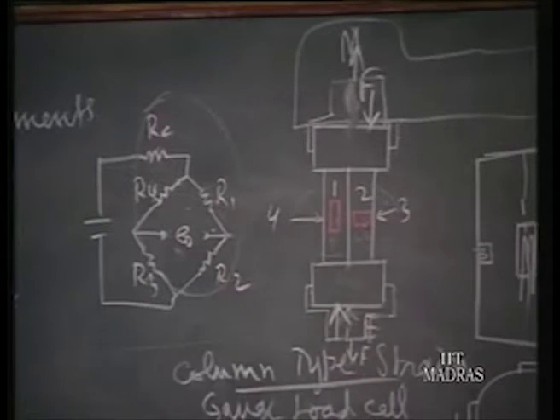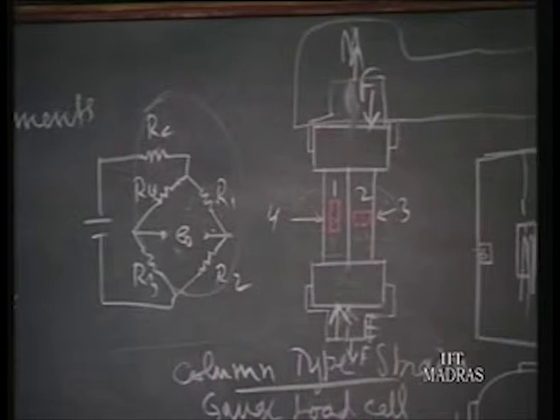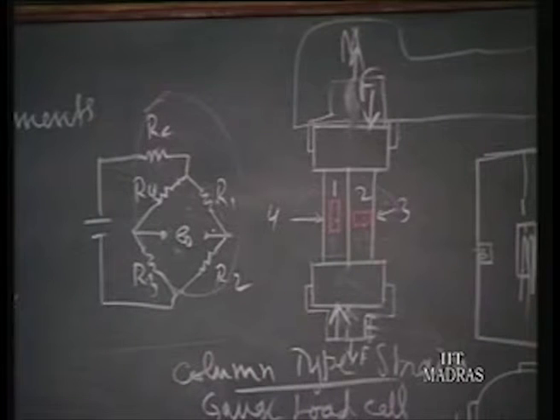If we fix the strain gauges on the existing member which has been designed for strength, then you will find the strain produced will be very small, 0.1 or 0.2 micro strain, which will not give rise to any output voltage. So when you want to fix the strain gauges on an existing member, at that place you have to weaken it so that there is sufficient strain, but you should not weaken it in a way that it goes into the plastic region, so the loading range should be just within the elastic region.